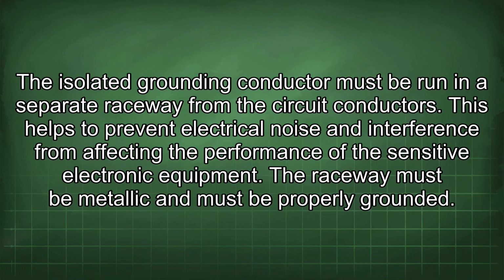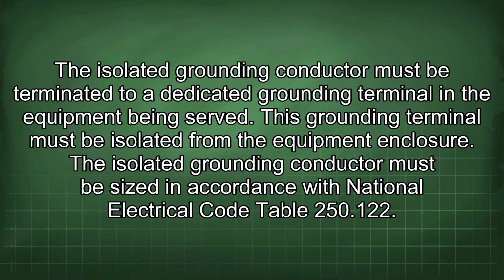The isolated grounding conductor must be run in a separate raceway from the circuit conductors. This helps to prevent electrical noise and interference from affecting the performance of the sensitive electronic equipment. The raceway must be metallic and must be properly grounded. The isolated grounding conductor must be terminated to a dedicated grounding terminal in the equipment being served. This grounding terminal must be isolated from the equipment enclosure.